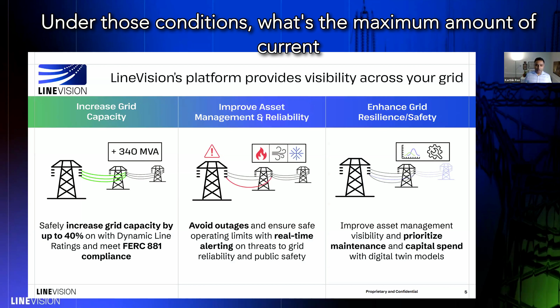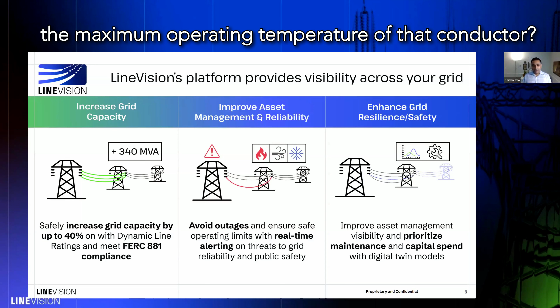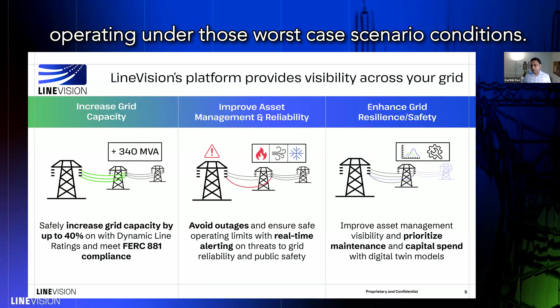Under those conditions, what's the maximum amount of current you can run through that line before you exceed the maximum operating temperature of that conductor? Whatever that number is becomes the fixed rating all year round. And of course, most of the time we're not operating under those worst case scenario conditions, so we're essentially leaving capacity on the table.